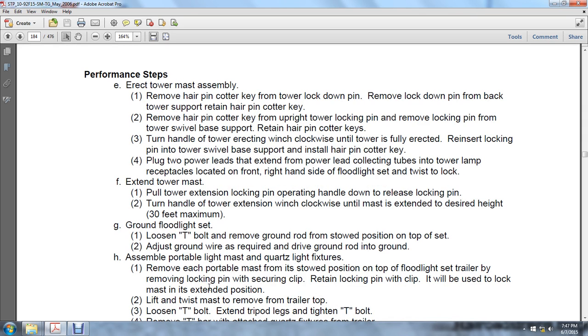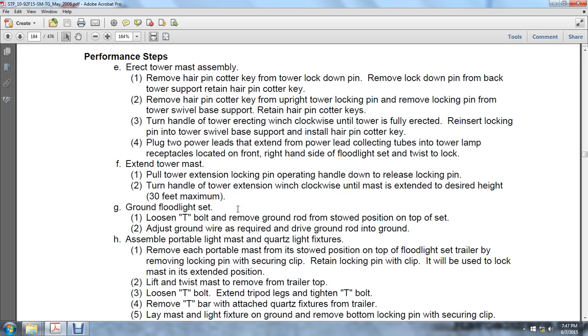Assemble the portable light mast of the quartz light fixture. Remove each of the portable masts from the stowed position on the top of the floodlight set of the trailer by removing the lock pin with the securing clip. Retain the locking pin with the clip. It will be used to lock the mast into extended position. Lift and twist the mast to remove it from the trailer top. Loosen the T-bolt. Extend the tripod legs and tighten the T-bolt.